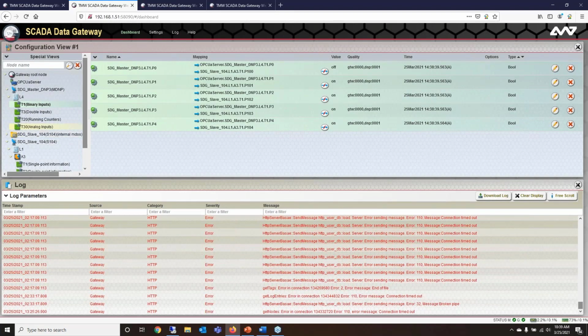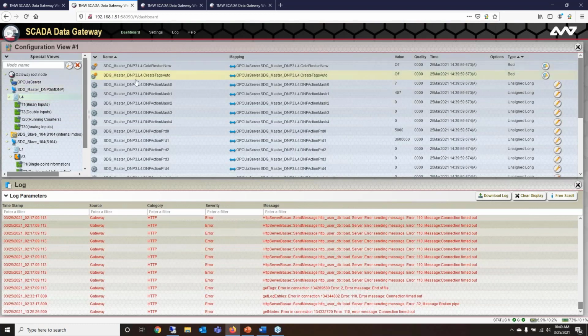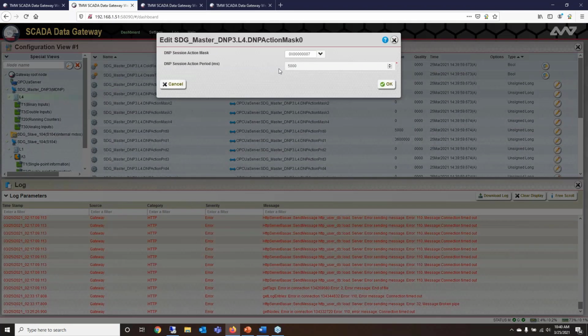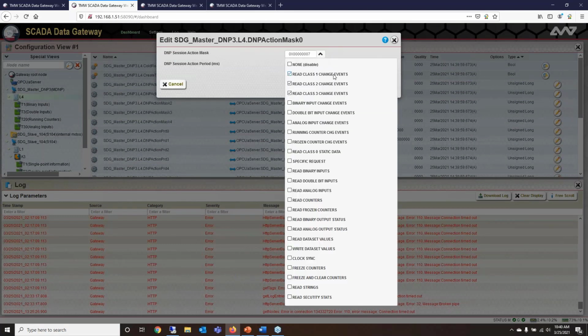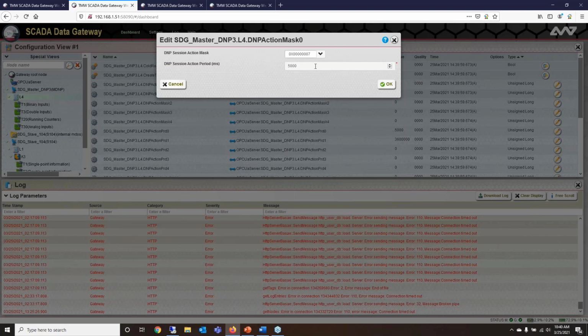So now let's take a look at how we're getting this data across. I'll go to this L4 here and take a look again at the action mask. In this situation I've got a drop-down, and you can see we're reading class 1, class 2, and class 3 change events. This is effectively doing event monitoring and polling for events rather than polling for everything during a set time, and again this is done at a 5-second period rather than the 15-second one we looked at before.